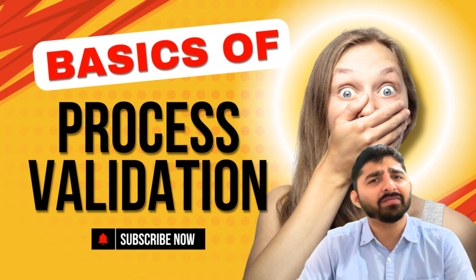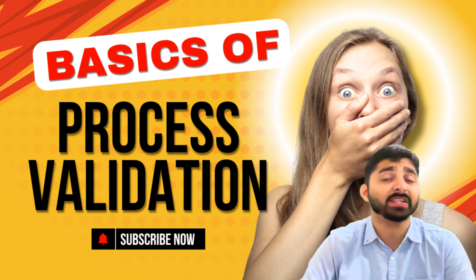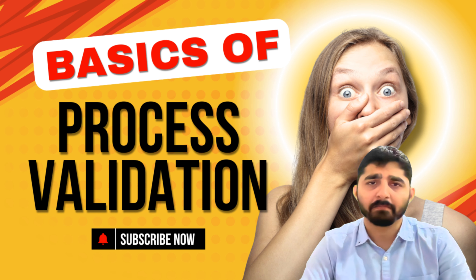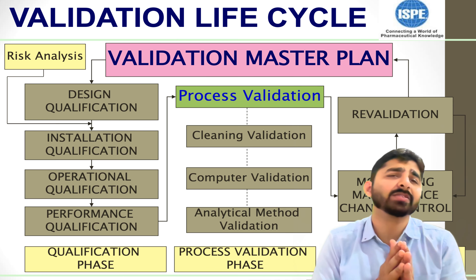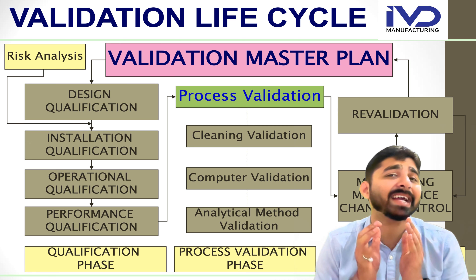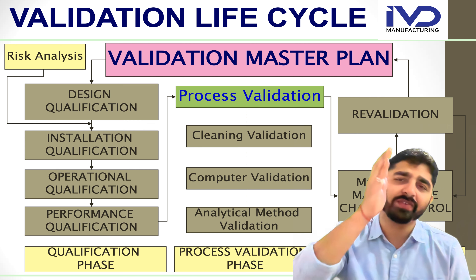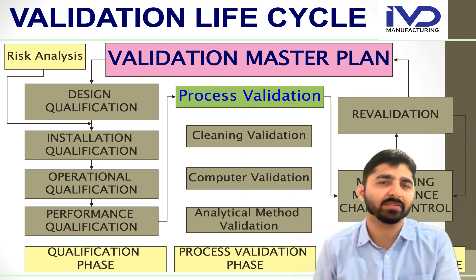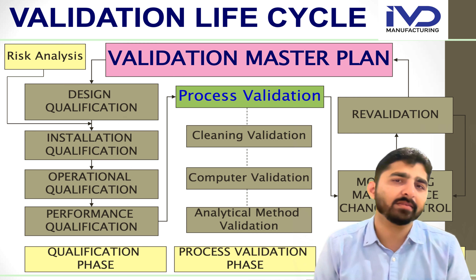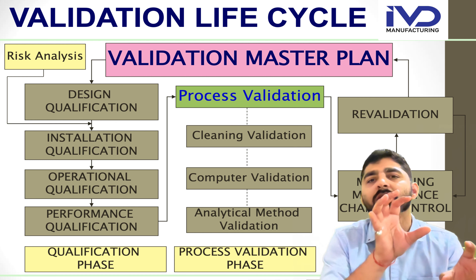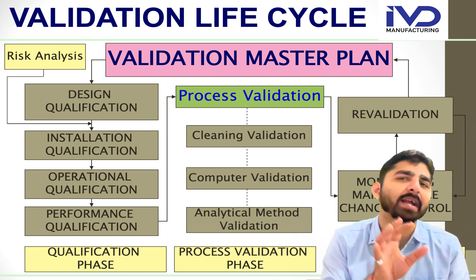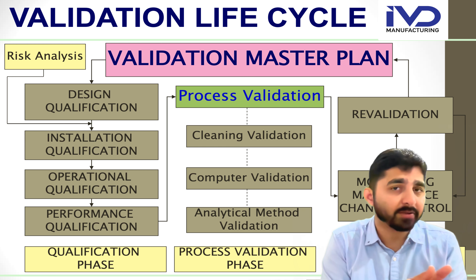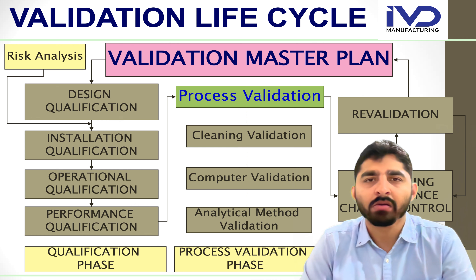Now let's talk about the validation life cycle, which is governed by the Validation Master Plan, or VMP. Any organization or company needs to stick to this plan. In the VMP, there are mainly three categories: the first includes all the qualification activities, the second covers the validation activities, and the third covers the revalidation phases. Within the VMP, there are four key phases: risk analysis, the qualification phase, the process validation phase, and the validation maintenance phase.